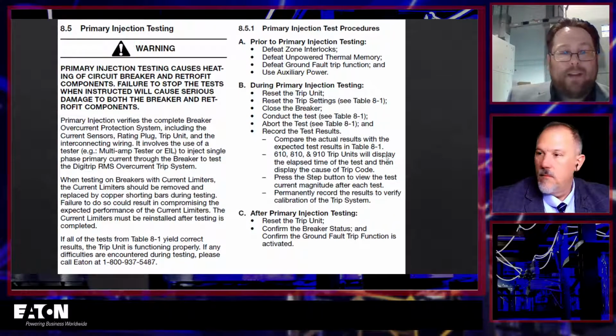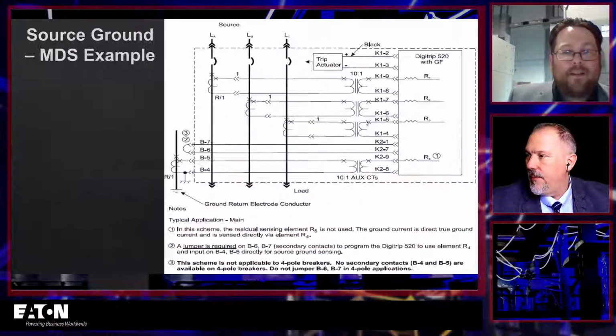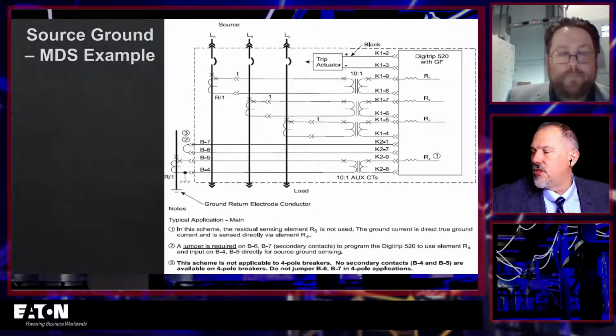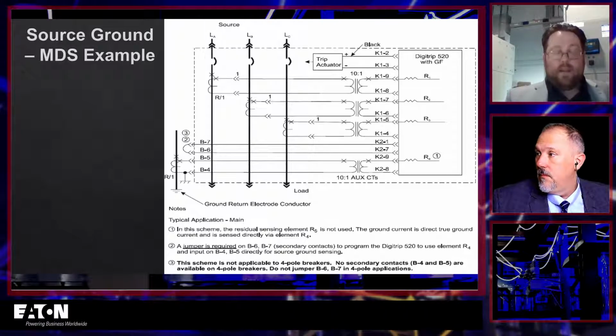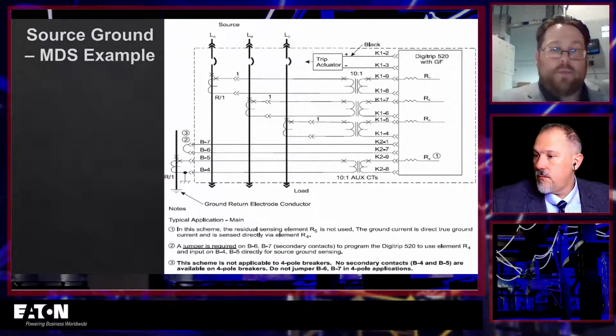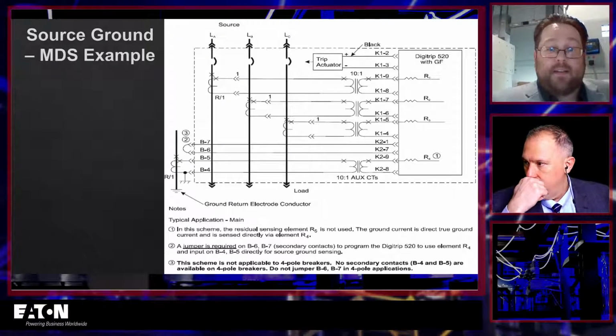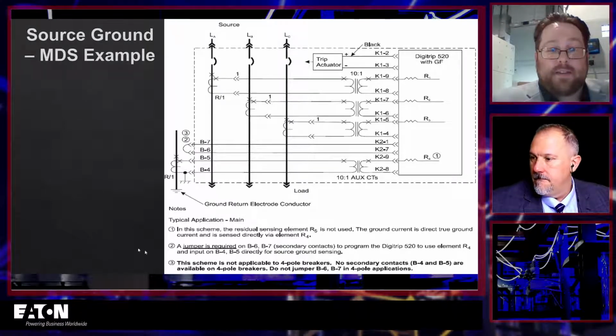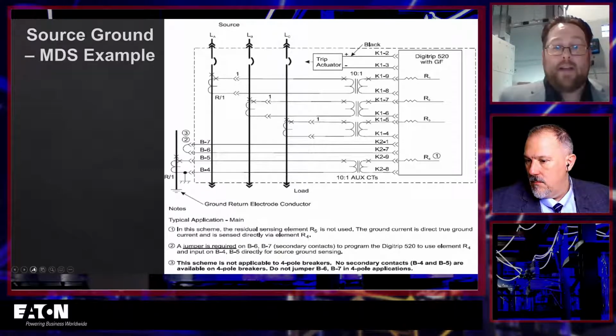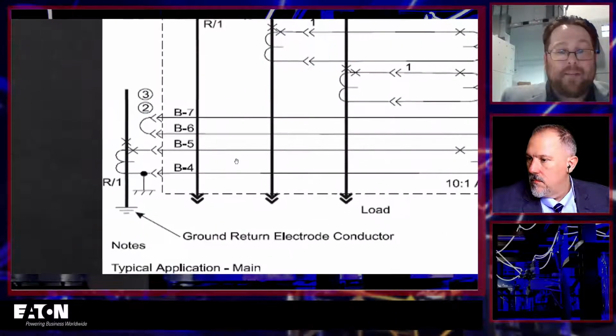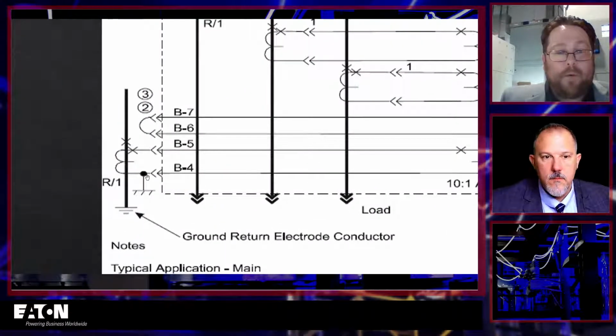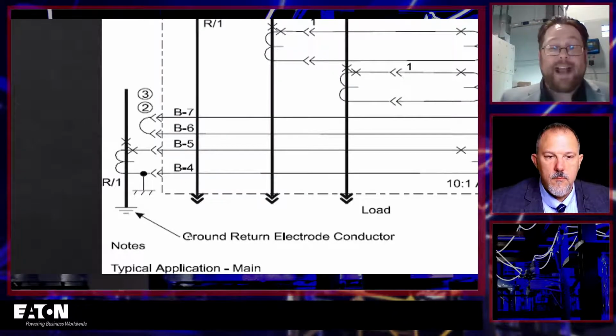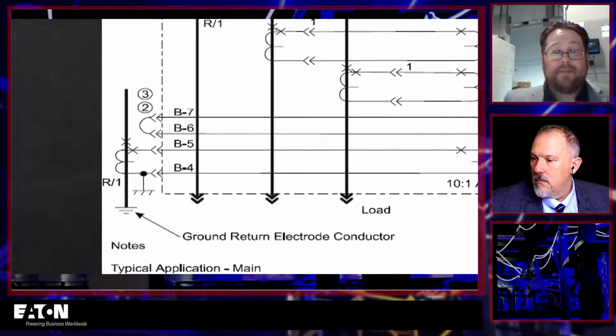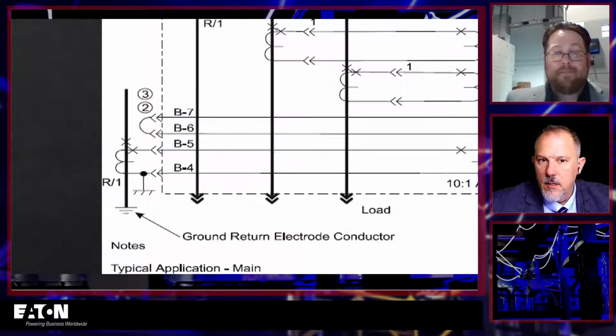Right. So, I'm going to go back to some of your slides. What's this one here? This is a Digitrip 520. So, source ground. What you see there is your phase CTs on the top, where it says R/1. Those would be your phase CTs, and then you have that source ground CT that you're highlighting down there in the bottom left-hand corner, B4 to B5 on that trip unit. That's the actual CT that's going to be on that grounding electrode to measure ground current.